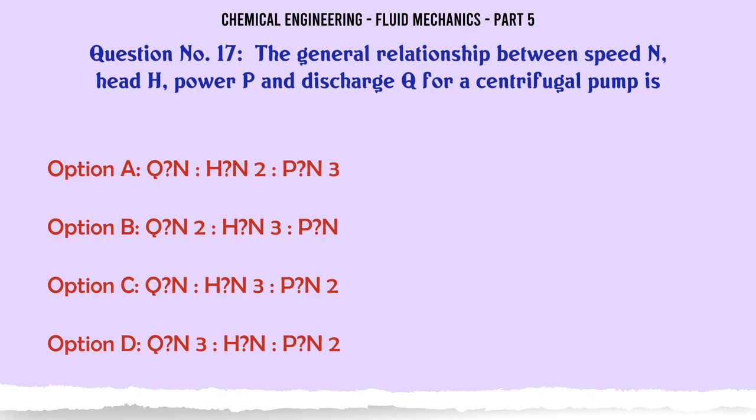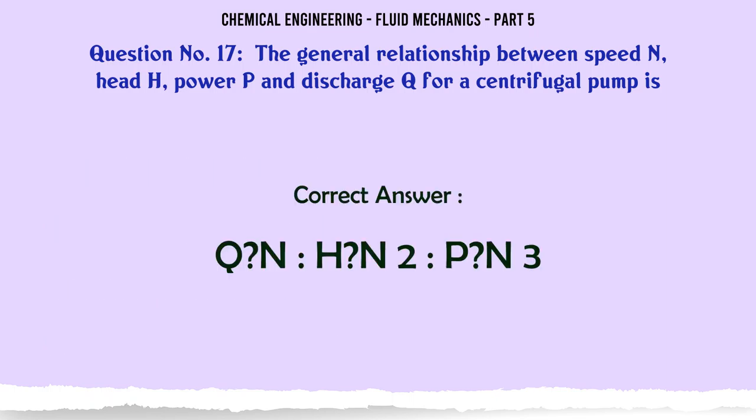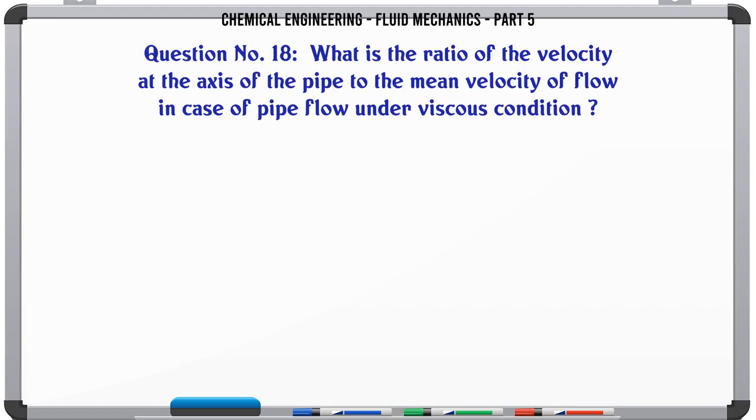The general relationship between speed n, head h, power p, and discharge q for a centrifugal pump is: a) q∝n, h∝n², p∝n³, b) q∝n², h∝n³, p∝n, c) q∝n, h∝n³, p∝n², d) q∝n³, h∝n, p∝n². The correct answer is q∝n, h∝n², p∝n³.